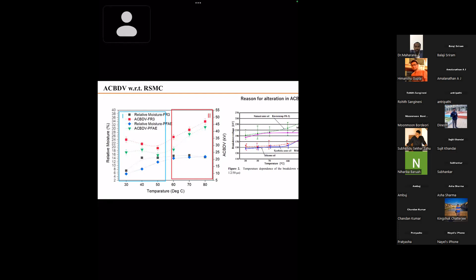With the increase in temperature till 50 degrees, the breakdown voltage is not fluctuating very much. If you see the standard deviation also, with the increase in relative saturation moisture content, the breakdown voltage does not fluctuate much. But beyond 50 degrees, there is a high spike, and you can get a significant difference in their dielectric strength. The reason for that we have analyzed in the further slides, but we need to note that before 50 degrees and after 50 degrees is the standard mark for us. We need to evaluate why it is happening like this.